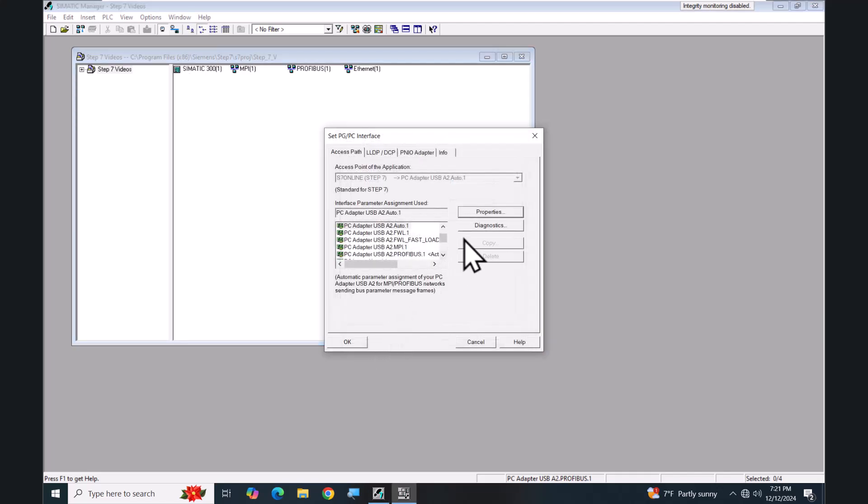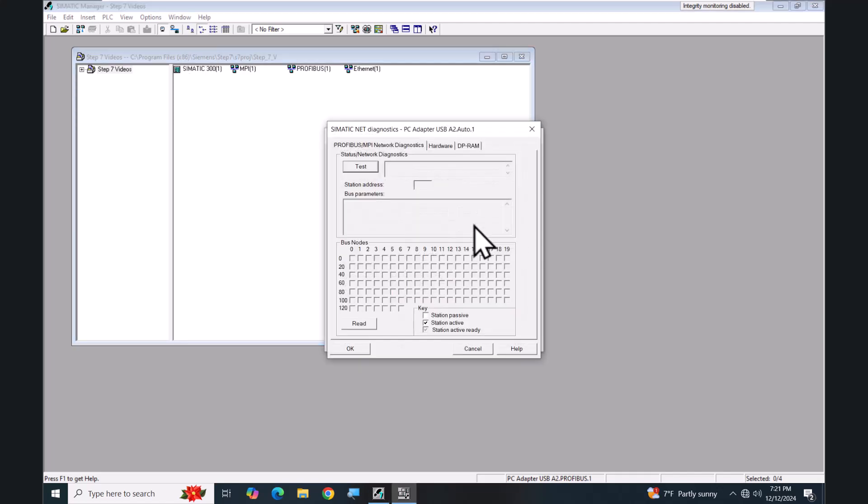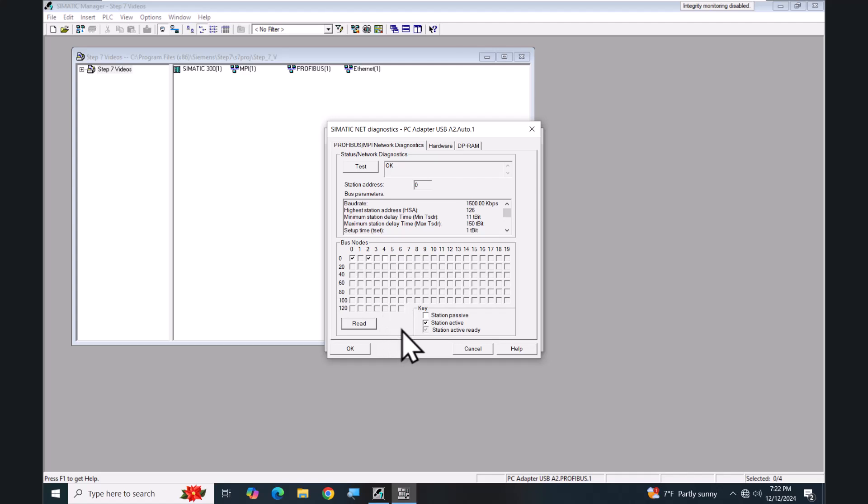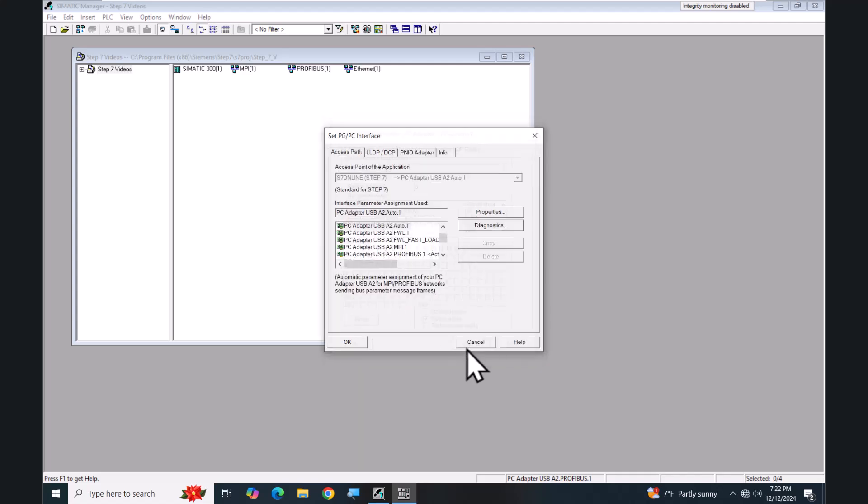You can also select the diagnostics button. You can do a test here. This will also show you the actual bus parameters that are currently in use. There is a Read button. This allows you to go out to read the individual devices and it will tell you whether there are active nodes or passive nodes on the network that you have access to. So zero is my programming device, two is my PLC and those are both active nodes. Station number four is a passive node which is an I/O drop.